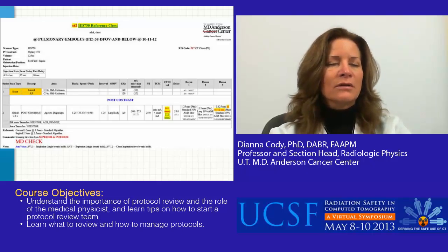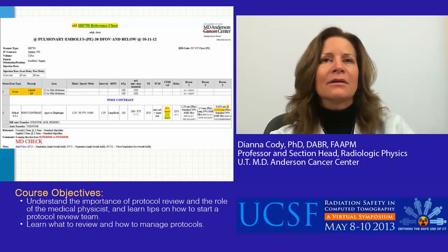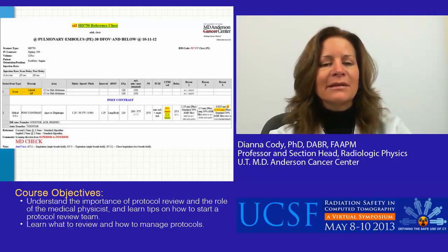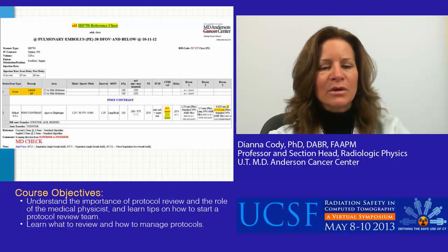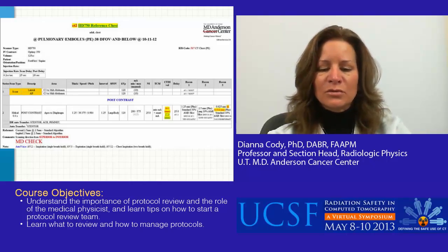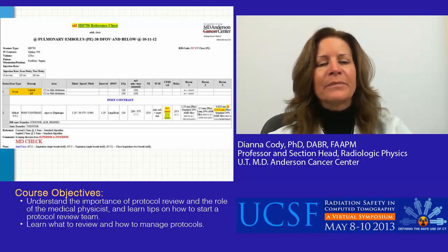This is our protocol document. So this is the descriptive page that we build based on this database that we are using. And so here you can see that there was actually more than one mismatch. One had to do with the name of the protocol, another had to do with the dose value that's shown here, and another had to do with the interval between images set on this third reconstruction set. So this is a tool that we've developed as part of our CT protocol review process.